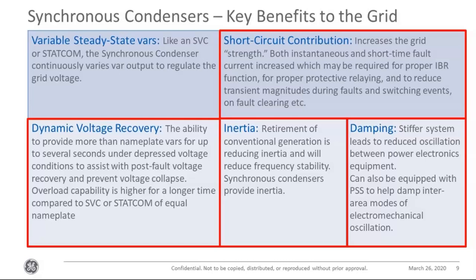They can help increase inertia, which helps frequency stability, and also helps make the grid stiffer, which is helpful for IBR operations. And lastly, damping, where the generally stiffer system itself leads to reduced oscillations between power electronics. But on top of that, we can equip these synchronous condensers with PSS to damp out some inter-area modes of oscillation. So that's a very brief summary of the talk. That's it from my end.